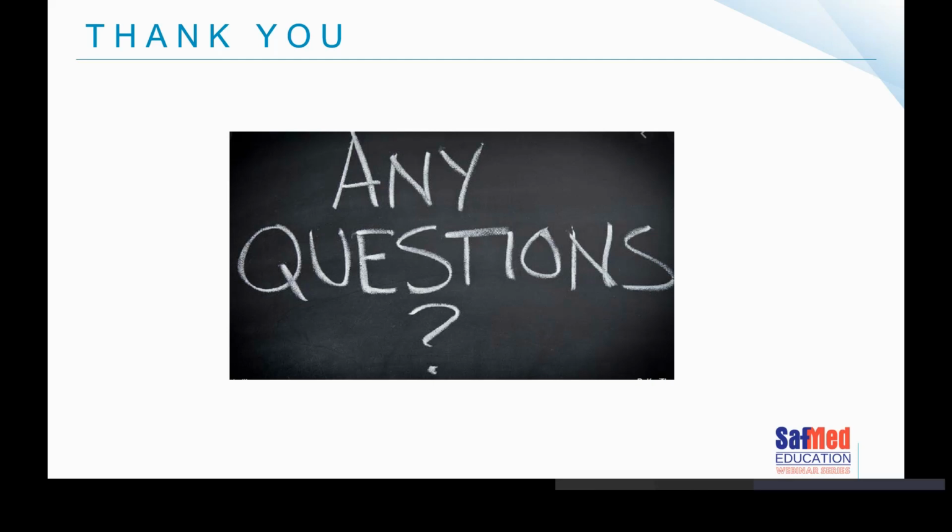Agreed, and I must say, Briette, that all the published papers say something similar about trying to determine whether an instrument is clean. Standard visual, naked eye inspection is really the least reliable. That's why these days there's a focus towards some form of scientific measure, for example using residual protein to test whether something is clean or dirty, and enhanced visual inspection, so trying to find ways to see better whether the instrument is clean or not, using magnification, lighted magnification, etc. These days they're getting onto fancy things called borescopes that you can put down instruments to see how clean they are or aren't. It would be quite interesting if we put a borescope through some of the corners of an operating table. I think we might be a bit scared.